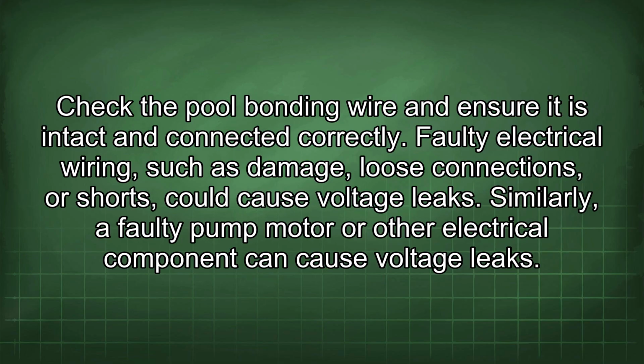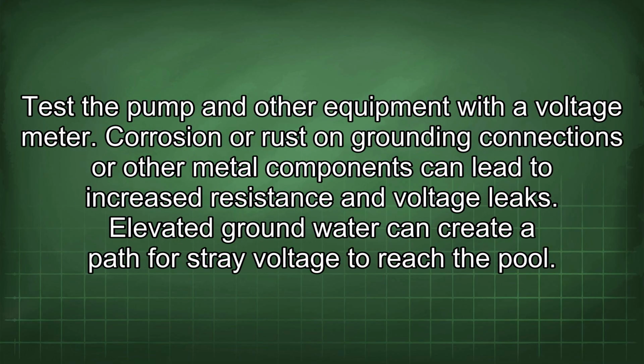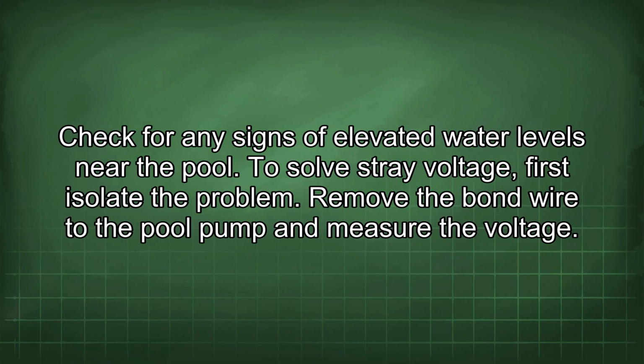Faulty electrical wiring, such as damage, loose connections, or shorts, could cause voltage leaks. Similarly, a faulty pump motor or other electrical component can cause voltage leaks. Test the pump and other equipment with a voltage meter. Corrosion or rust on grounding connections or other metal components can lead to increased resistance and voltage leaks. Elevated groundwater can create a path for stray voltage to reach the pool. Check for any signs of elevated water levels near the pool.